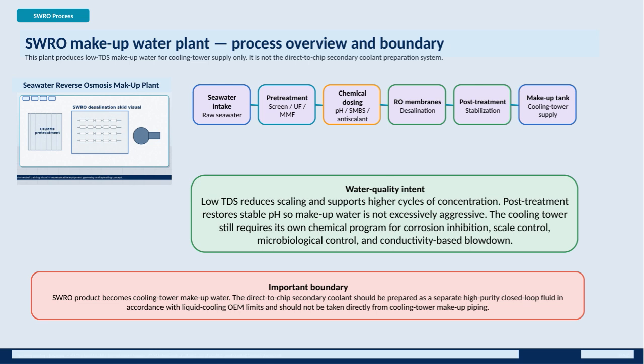maintaining efficient cooling operations. It's important to note that this plant is not responsible for preparing the direct-to-chip secondary coolant system. Starting from the seawater intake, raw seawater is first drawn in. Then it goes through pre-treatment stages that include screening, ultrafiltration, and multimedia filtration to remove particulates and prepare the water for desalination. After pre-treatment, chemical dosing is applied. This includes adjusting pH and adding sodium metabisulfite and antiscalants to prevent membrane fouling and scaling.